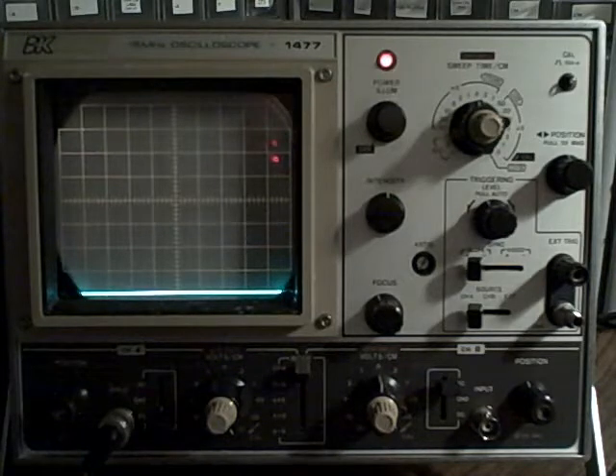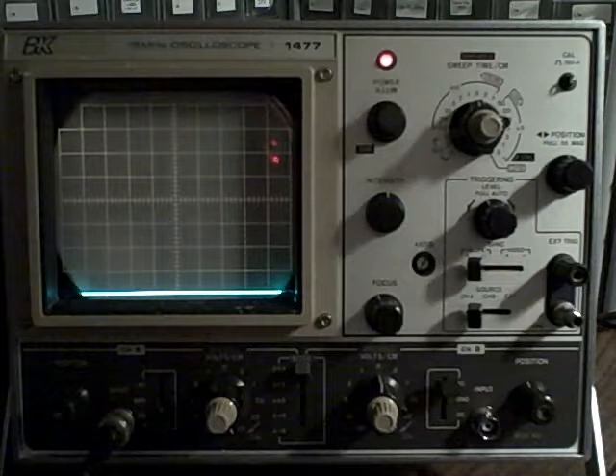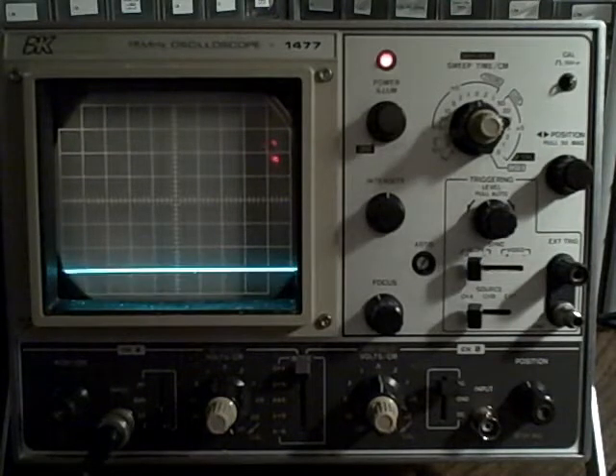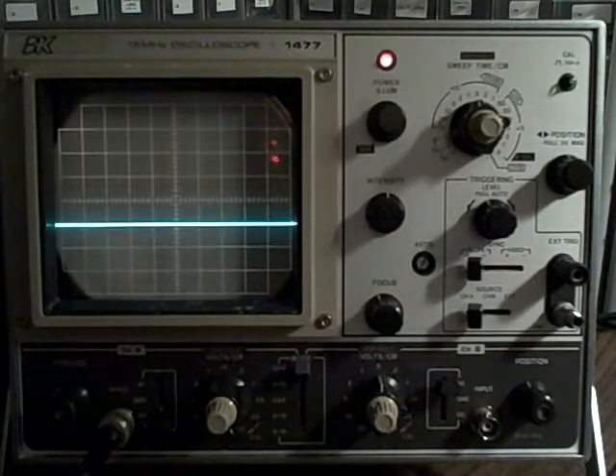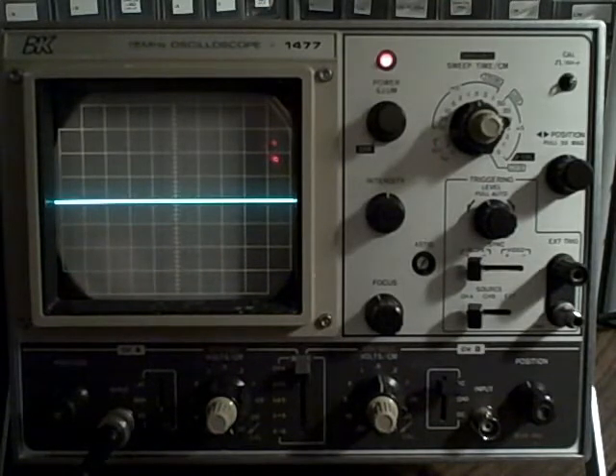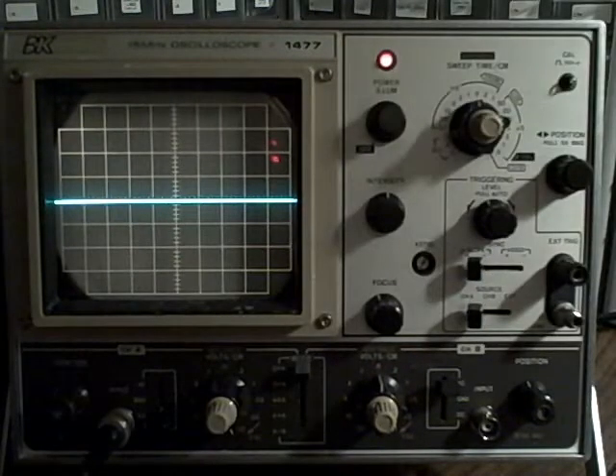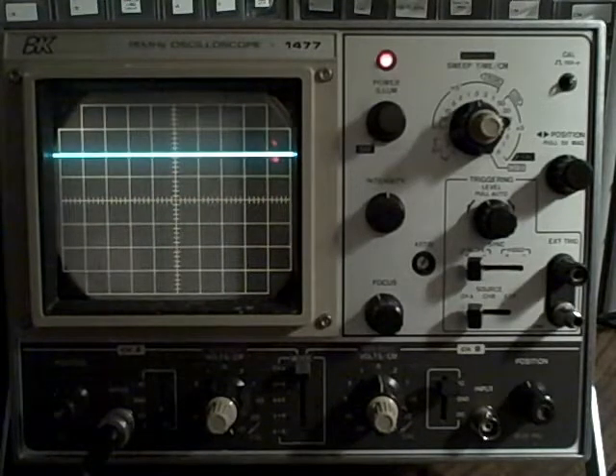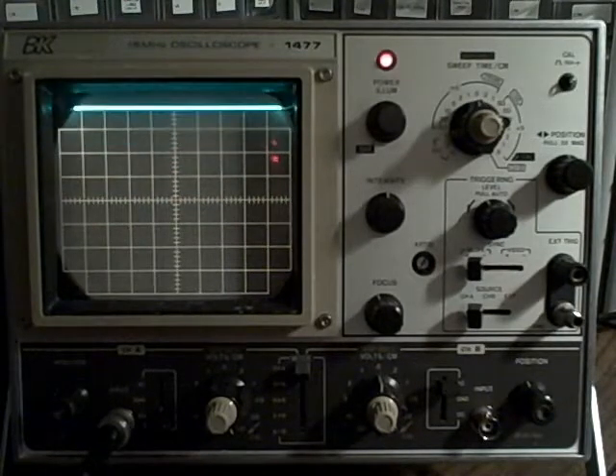We are on the 0.01 volt per division, and we are dividing by 10 through our probe. So in order to get 0.01 at the scope, that means we have to put 0.1 in at the probe tip, and that's what we're going to do. So we'll have steps of 0.1. We should see ourselves go up each division. So here's step 1, 2, 3, 4. Let me turn the illumination up for you. 5, 6, 7, 8. Perfect.